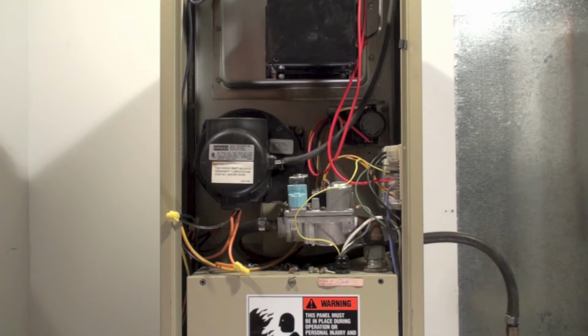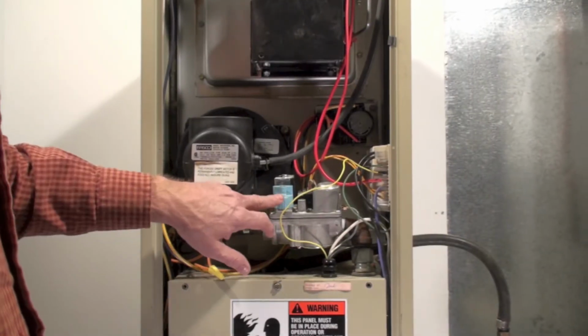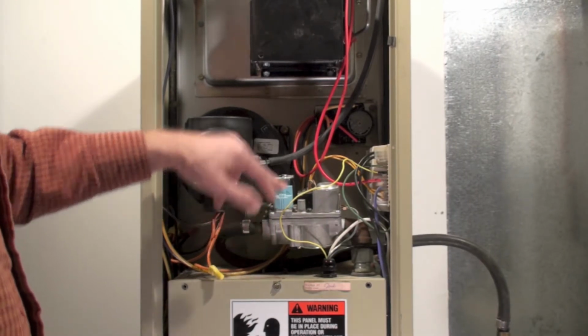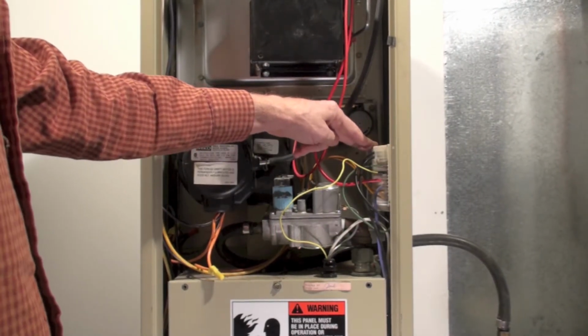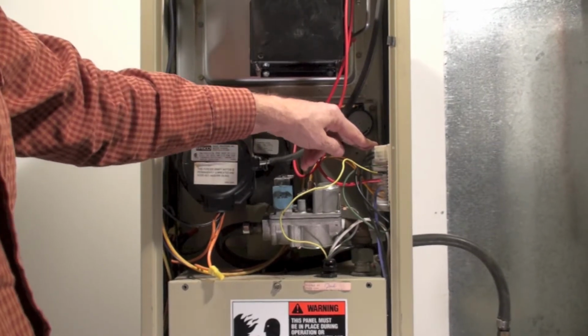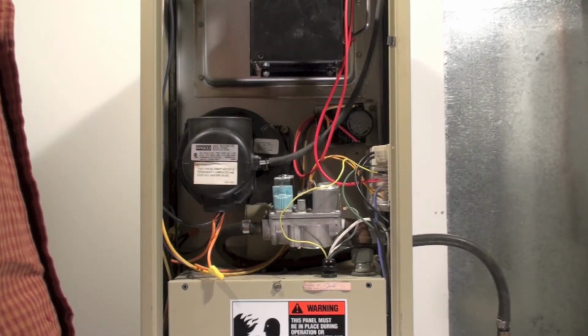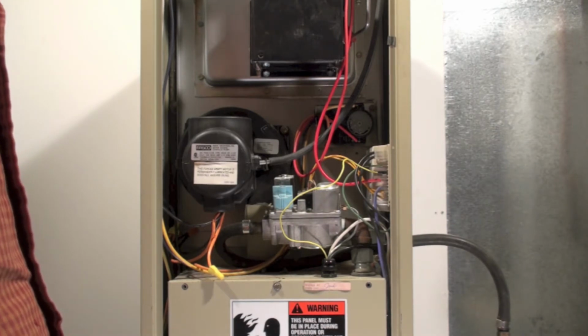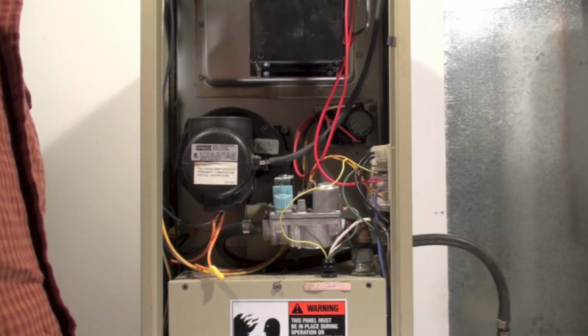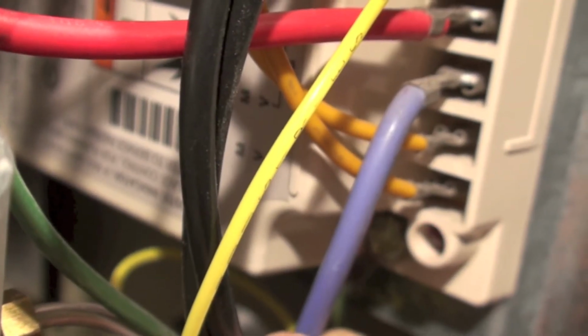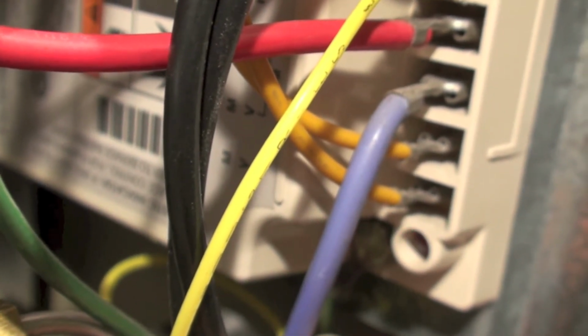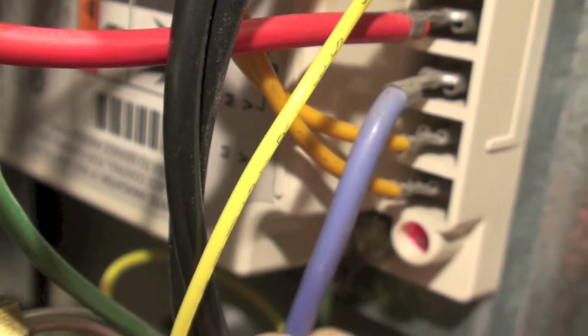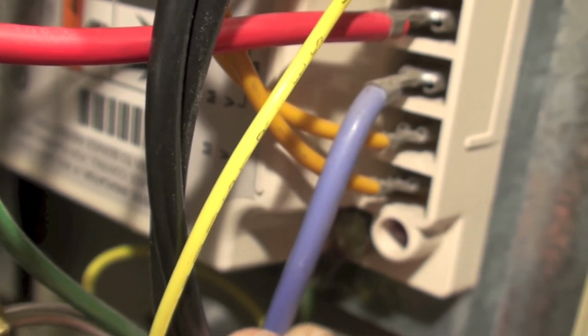I've heard the hot surface igniter come on, and the ignition should come on pretty soon. Okay, I'd go ahead and shut the gas valve off. Let this thing go through 3 cycles and be sure that it starts blinking and shuts off after 3 times. Goes into hard lockout. Just a safety check on it. So you're going to be looking for the flashing light on this thing after the 3 tries to indicate that it has gone out on hard lockout.